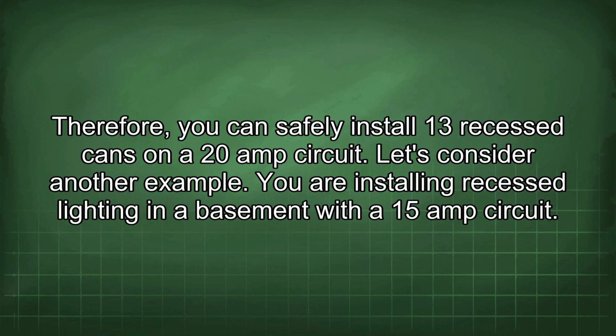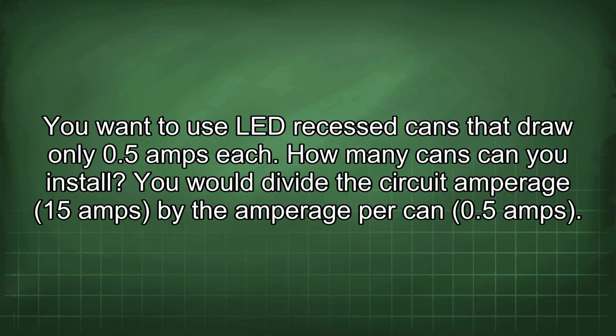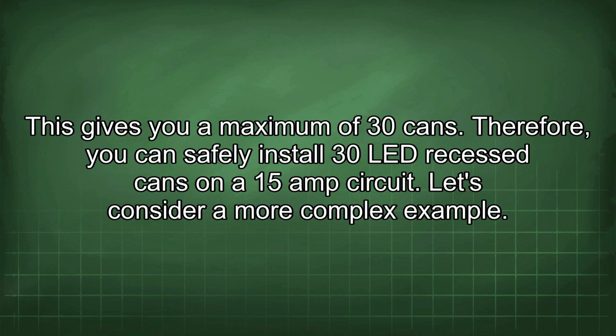Let's consider another example. You are installing recessed lighting in a basement with a 15 amp circuit. You want to use LED recessed cans that draw only 0.5 amps each. How many cans can you install? You would divide the circuit amperage, 15 amps, by the amperage per can, 0.5 amps. This gives you a maximum of 30 cans. Therefore, you can safely install 30 LED recessed cans on a 15 amp circuit.